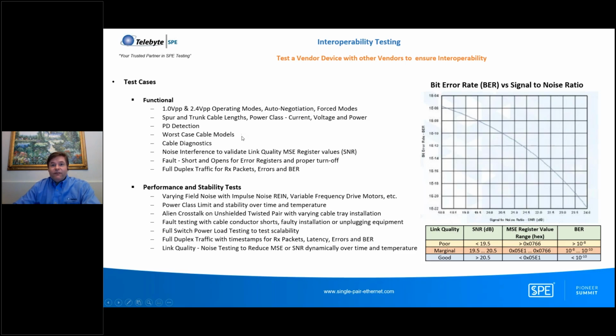We have to test over variable cable lengths, short cable lengths and longer cable lengths, maybe with different power classes if it's a field switch. We have to test that the PD detection is working. We want to test over worst case cable models. We want to test the cable diagnostics of the devices, if they can measure the quality of the cable. We want to test with noise, so we can add noise interference.